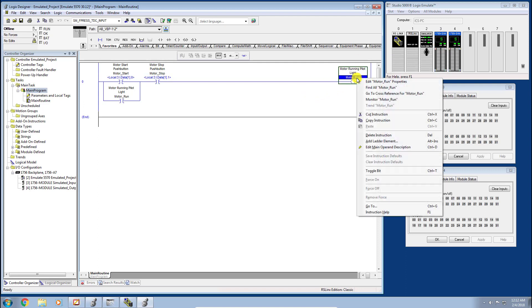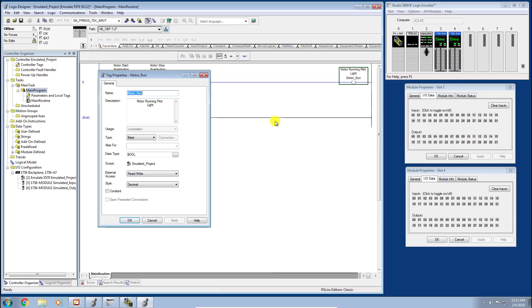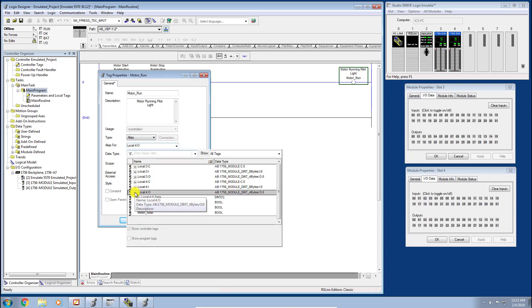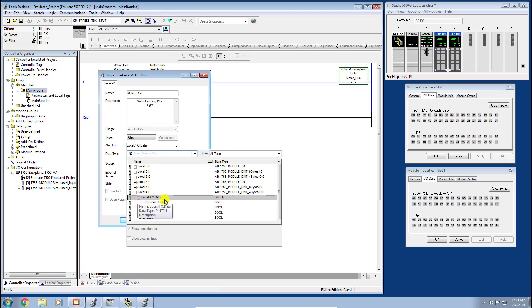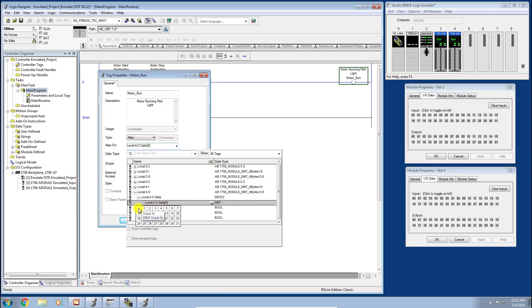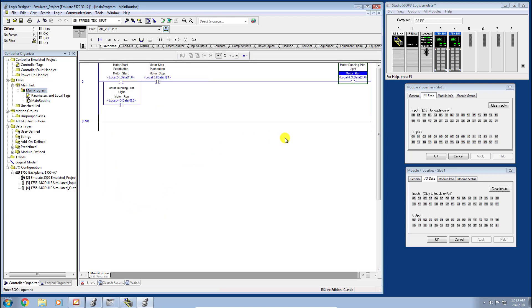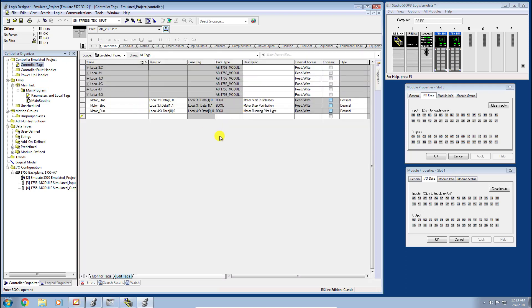Let's go ahead and set up this output. Again, that's going to be on slot 4. Let's change that to alias. We want our slot 4 output word, our data word, and we want to hit the flyout and we'll make it bit zero. That's effectively it. Again, an alias tag is nothing more than a tag that represents another tag or a pointer to another tag. We're creating our global tags, our controller tags that are now an alias for these actual discrete input-output points.